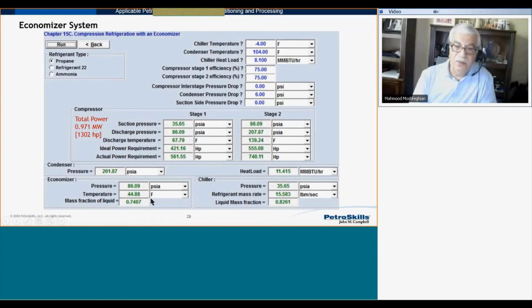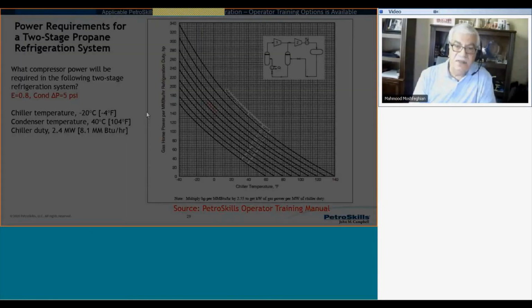So by doing this arrangement, with lower compression power requirement, normally it could be in the range of 15 to 25%, depending on the process. And this is the equation to determine the interstage pressure. So chiller pressure, or suction pressure of the first stage, times the discharge pressure of the second stage. Take the geometric average. That gives us 86 psi at the interstage pressure.